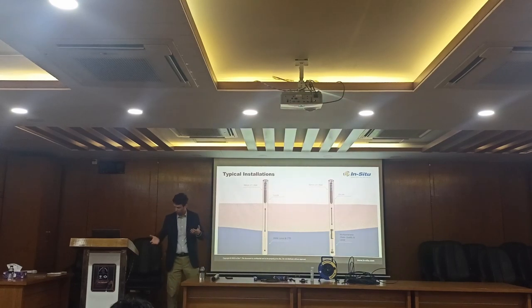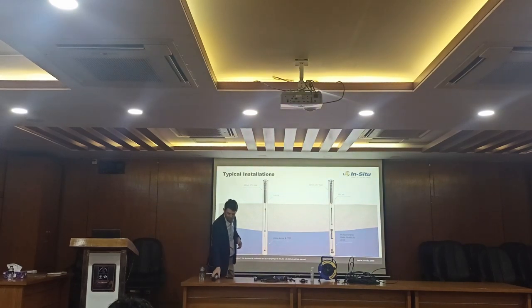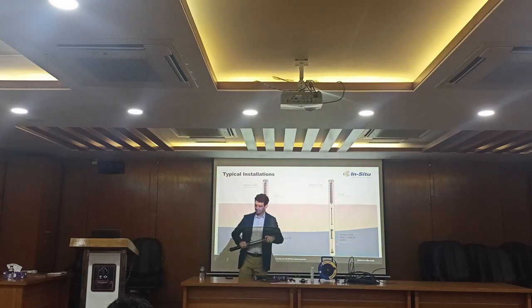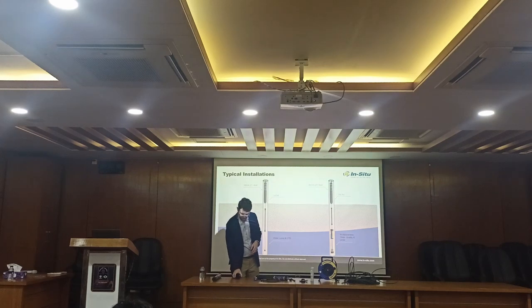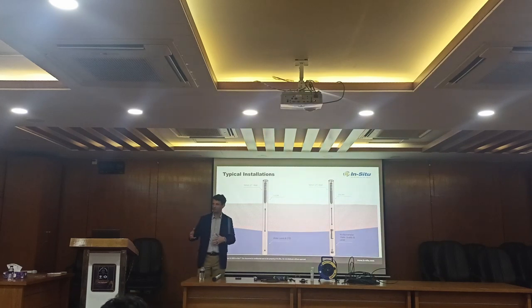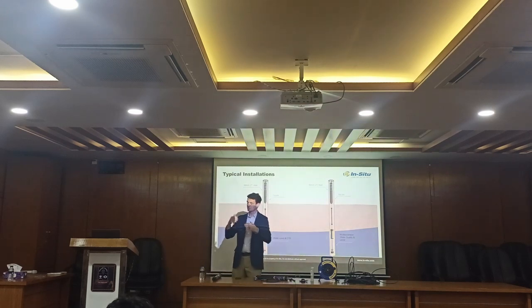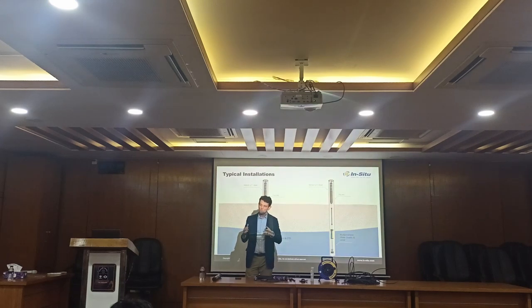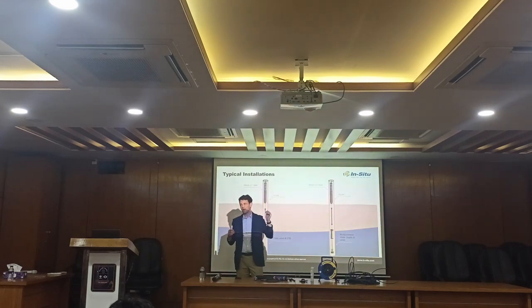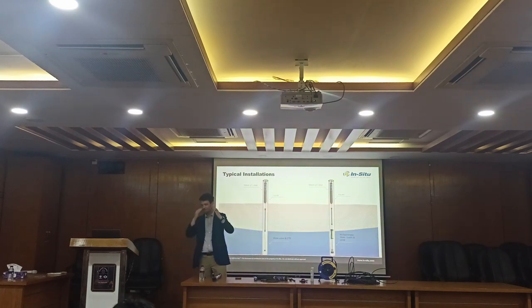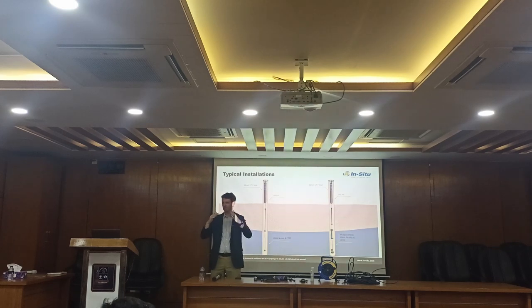So for those who didn't hear that, the question was around calibration of turbidity and chlorophyll sensors—two optical sensors. The really nice thing is, yes, can they be calibrated? Absolutely, and they should be used at times for calibration and checking. However, when they come from the factory, one interesting thing about what makes it an optical sensor is that they have an LED light that emits out to the detector. Typically, an LED light will degrade over time, and that's when you need a calibration—because that light is changing, or maybe the detector is changing.